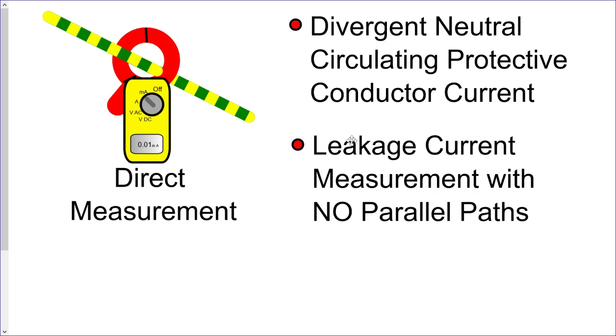Remember, if you're still measuring currents at the point after you've isolated the system, then you should not be disconnecting anything. You should be contacting the DNO. Other ways in which we can utilise this direct measurement again is for leakage current. Generally, it's only really ideal for when we're working on a circuit where there's no parallel paths. Yeah, so there's no current circulating elsewhere within the system.